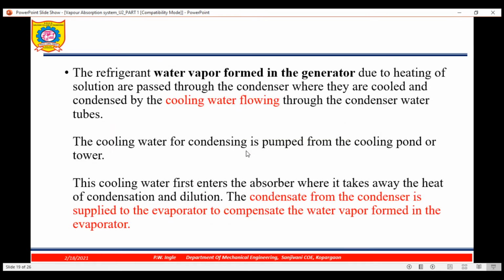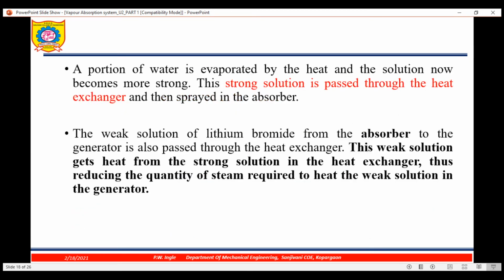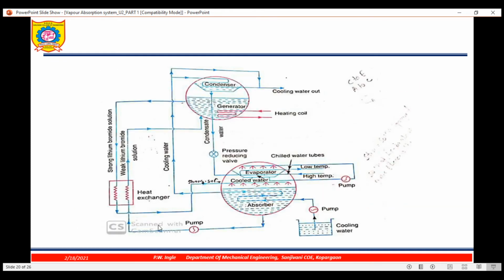And next is the weak solution of lithium bromide from the absorber to the generator, which is passed through the heat exchanger. This weak solution gets heat from the strong solution and thus reduces the quantity of steam required to heat the weak solution. Now what is the use of this heat exchanger?